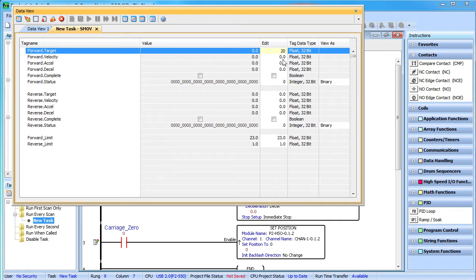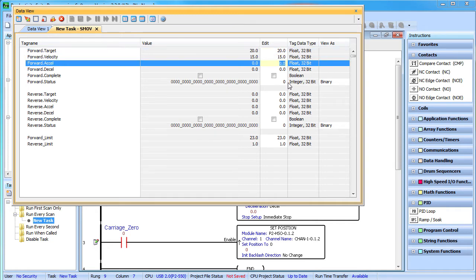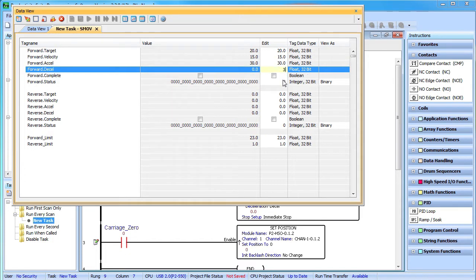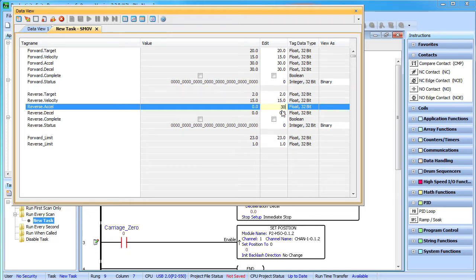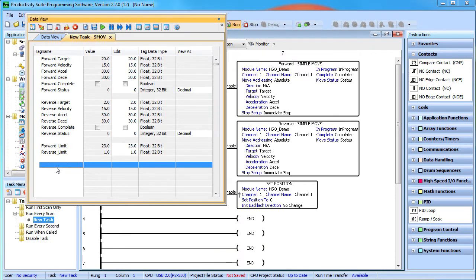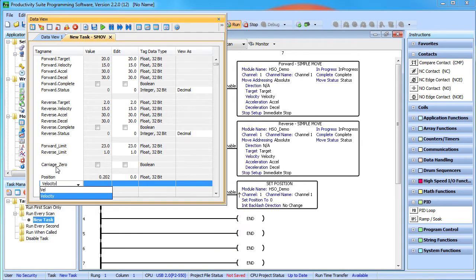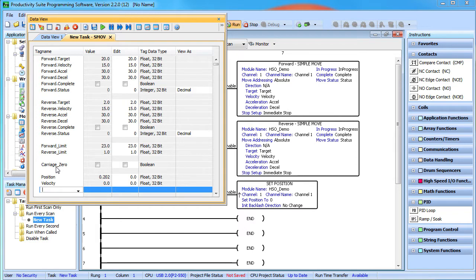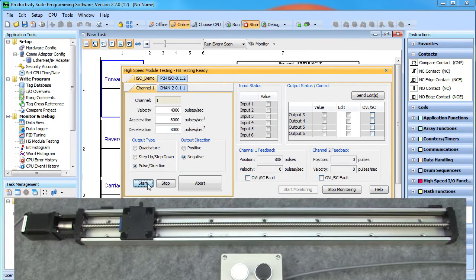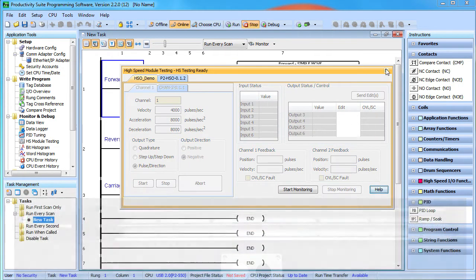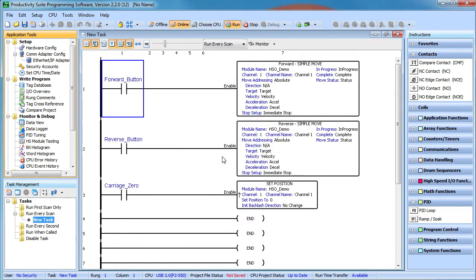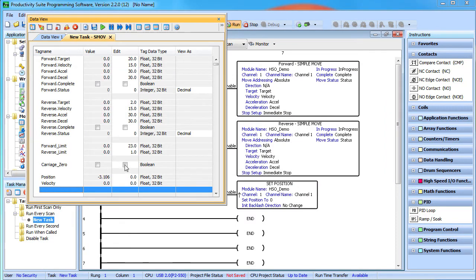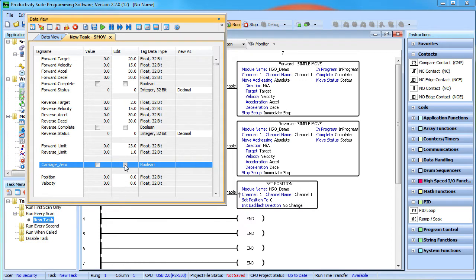We want to move to 20 inches in the positive direction at a max rate of 15 inches per second and we'll accelerate and decelerate at twice that rate. For the reverse direction we'll target 2 inches as our destination and use the same velocity and acceleration. Let's also add the carriage zero contact and the real time position and velocity tags to our data view. We'll do homing in a separate video so for this demo we'll stop the CPU and just manually move the carriage to zero using the high speed module testing tool. Now we put the processor back in run mode and toggle this contact to set that carriage position to zero.